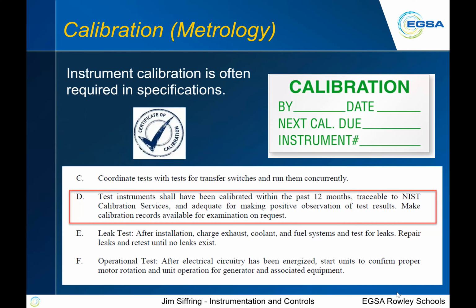We want to talk about having your standards calibrated. Whatever your test equipment is needs to be calibrated and up to date. You'll see this little segment here, item D, where test instruments shall have been calibrated within the past 12 months, traceable to NIST calibration services and adequate for making positive observation of test results, and then make calibration records. But anyway, that's a very standard line in a specification for a genset.